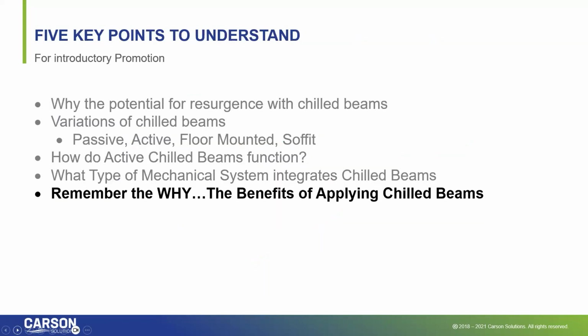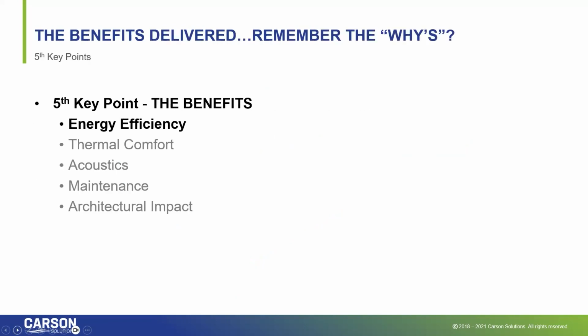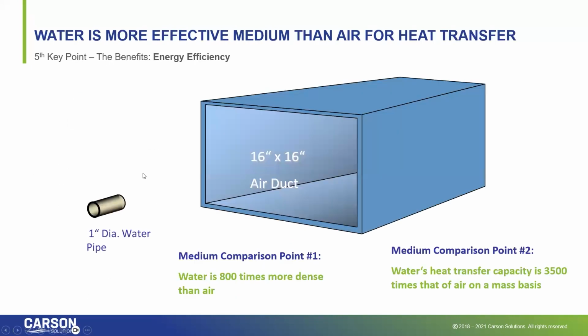So remember the why and the benefits that we receive by applying chill beams: energy efficiency, thermal comfort, acoustics, maintenance. So why? Water is just a much more dense, more effective medium than air for handling the BTUs within the space, and moving air with a fan is not as efficient as moving water with a pump as well.